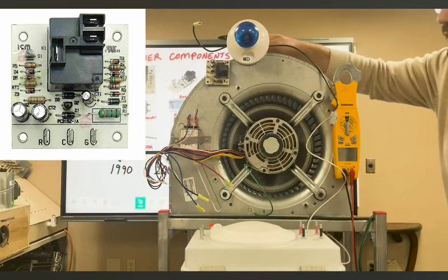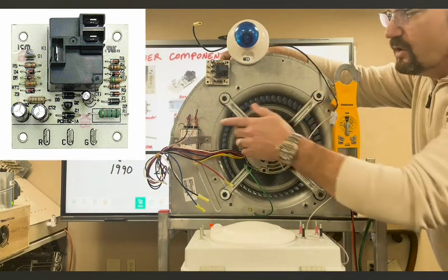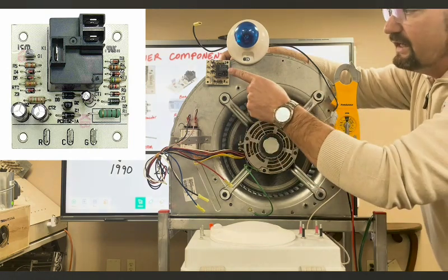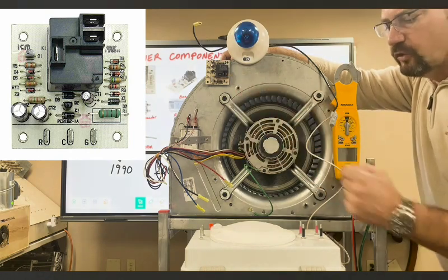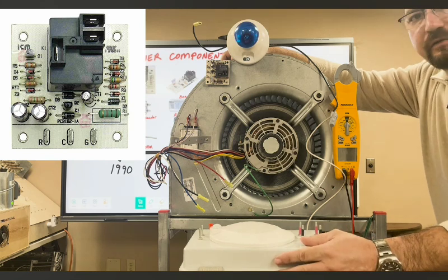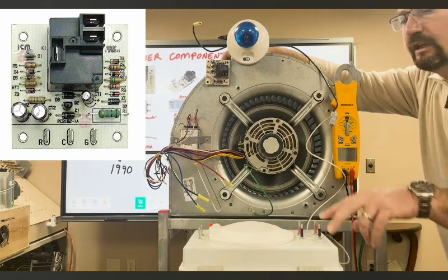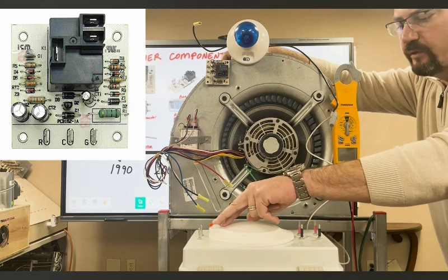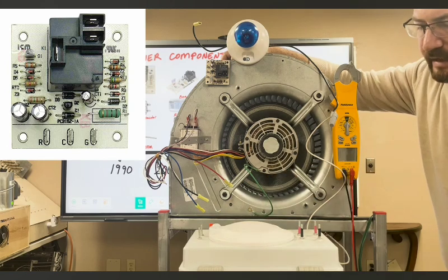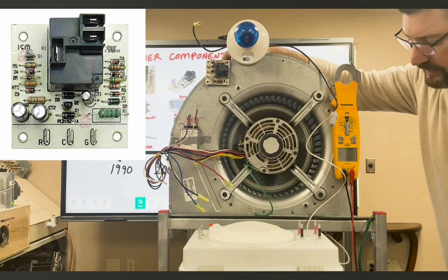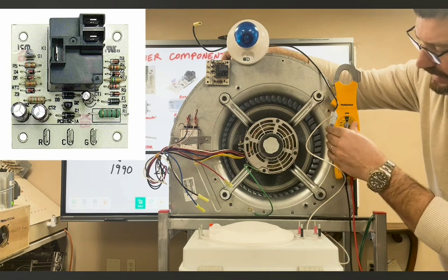Stay tuned. Okay, we're over at the blower motor. We got a PSC motor, run capacitor. We got the ICM 255 blower control board. We have our power supply down here where we have a live 240 volts and a live 24 volts off the transformer. I'm going to go ahead and demonstrate that with the meter. Go ahead and show you that we have live power.